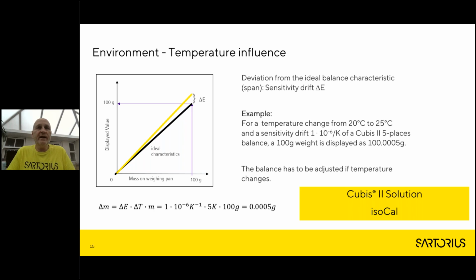So each balance, once again, will have a classification or a specification for temperature sensitivity. In other words, how much will the slope of the balance change with changes in the ambient temperature in the laboratory? This is normally given as a number of parts per million per degree Celsius or degree centigrade or Kelvin. For example, on a 5 decimal place balance, the specification is 1 part per million per degree. So if we calculate this out on a 100-gram weight, we would have an error of 100.0005. Once again, we have to adjust the balance if the temperature has changed in the laboratory.